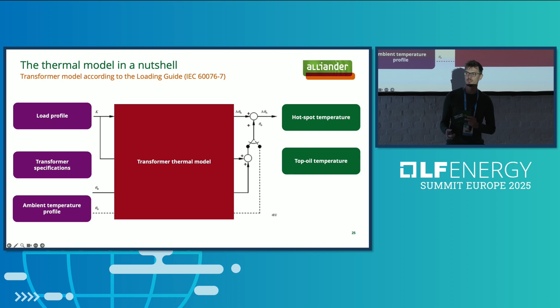So this model we can then use to, as I said, determine cyclic limits or to scale up the static limit of our transformer. The way we do this is by closely measuring the results, by calculating what kind of thermals are happening under its current load. Then if it does not reach its limit, we scale up our load and calculate again. And we repeat this process until we reach a certain limit where we think, all right, this is an acceptable area where we can increase our transformer to.